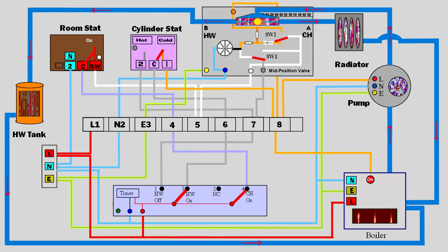With no volts on the gray, the valve would return to its default position. But SW2 is feeding the motor with pulsed DC via the diode and resistor with about 100 volts, so it keeps the valve in the stalled middle position with sufficient power to overcome the return spring tension with a type of magnetic effect.